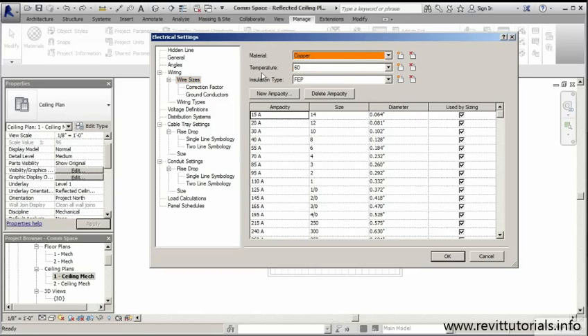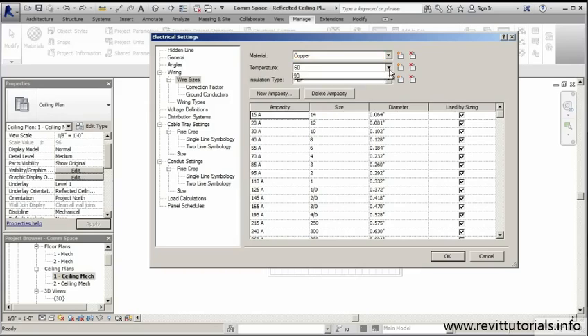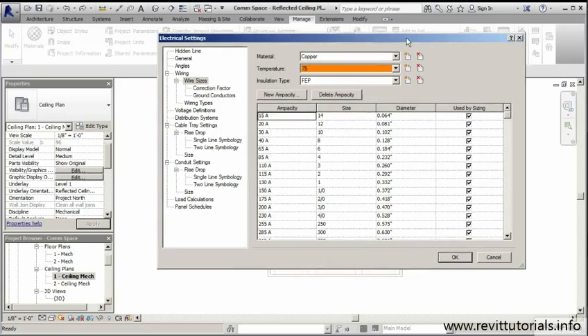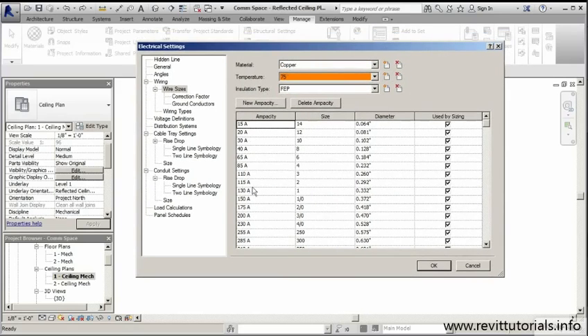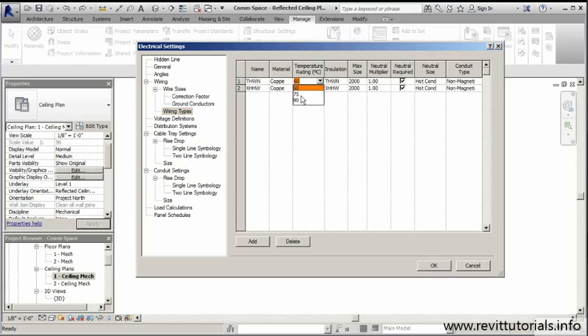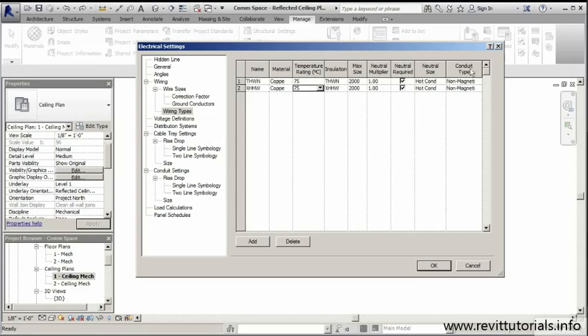We can also make adjustments to the temperature we want to specify for those wires. Right now, by default, we're set at about 60 degrees. I'm going to go to my dropdown and change that to 75 degrees. This will be better for our project. Not only can we adjust the sizes and material, there's also wiring types. You can see we've got names and material. A lot of the things we were working with in our previous window are located here. I'm going to make some changes to my temperature ratings, going from 60 to 75 degrees. I'm going to keep my wiring at copper, which is perfect. We're not too worried about conduit since we're not modeling any conduit in this course. We're going to make only those two changes.